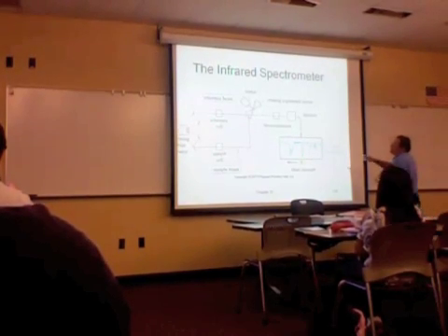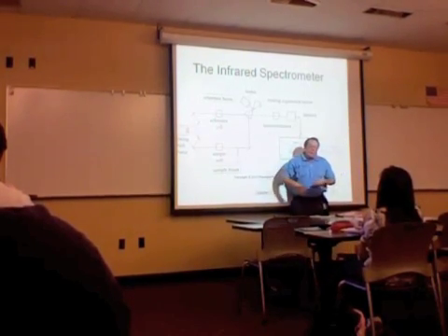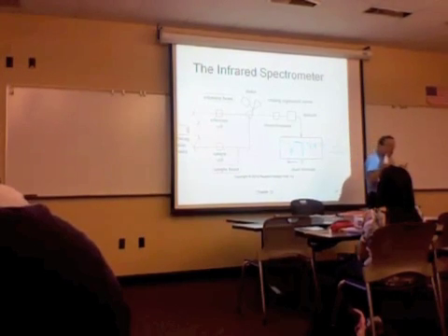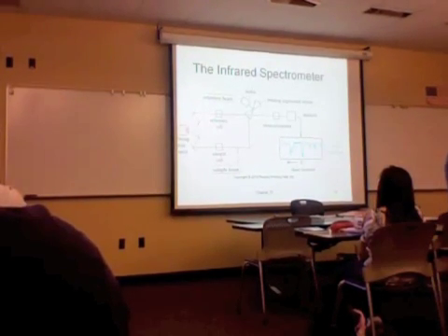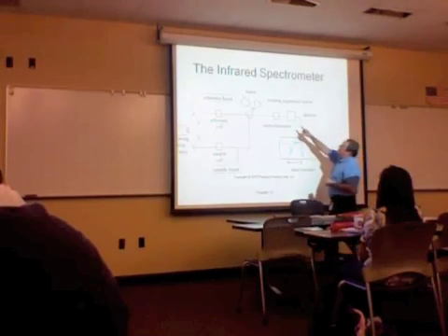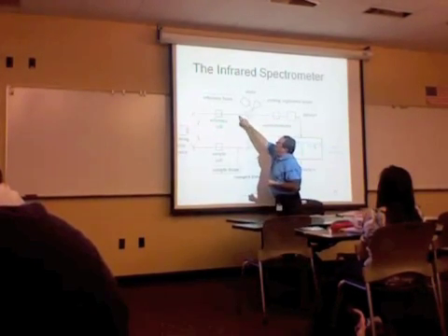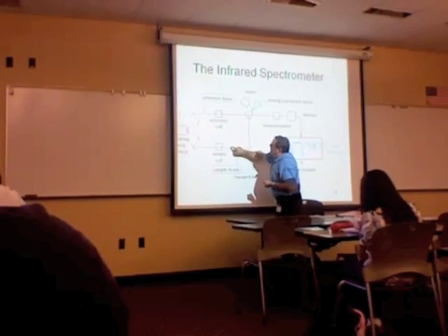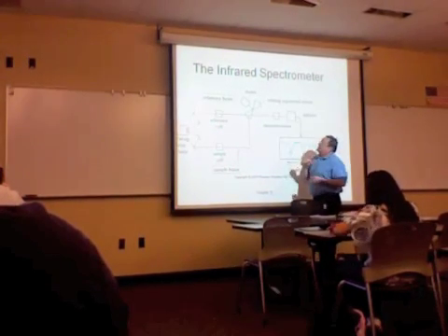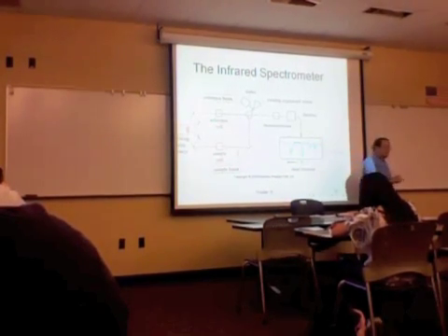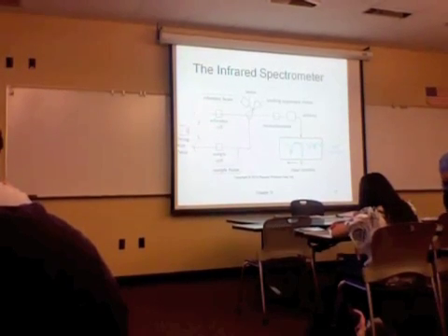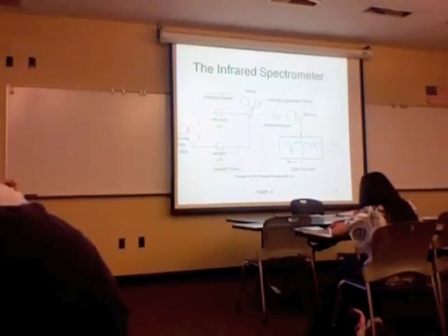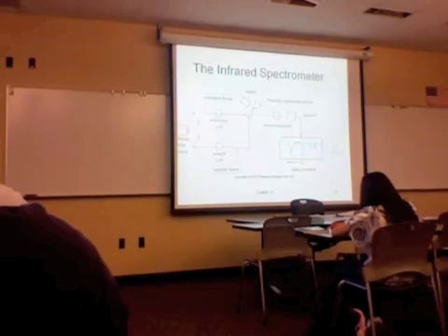This thing would be under electronic control, and as the sample is being analyzed, the monochromator would scan through the different wavelengths of the infrared, and then the alternating slices of data from the reference or the control side versus the sample side would hit the detector, and the detector would be mechanically controlled so that it would automatically subtract the reference cell from the sample cell and know the wavelength at which we were.